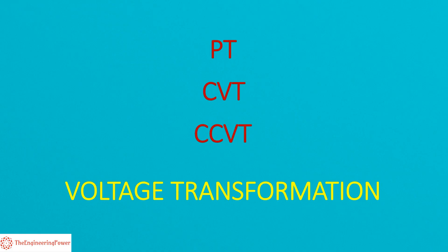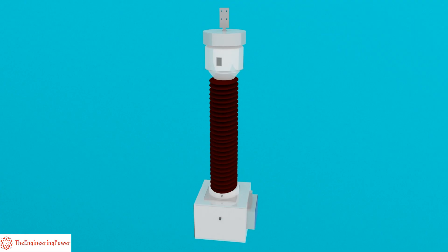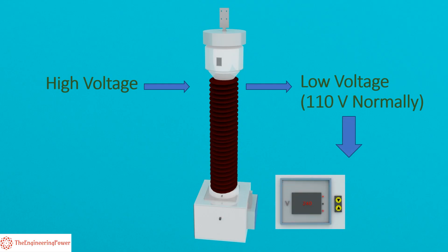We know that high voltages in substations cannot be measured directly and also cannot be fed to relays and meters. So potential transformer basically converts these high voltages to a safe value which is normally 110 volts, which can then be fed to meters and relays for measurement and protection purposes respectively.